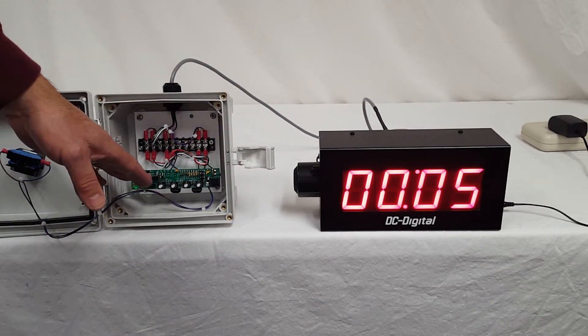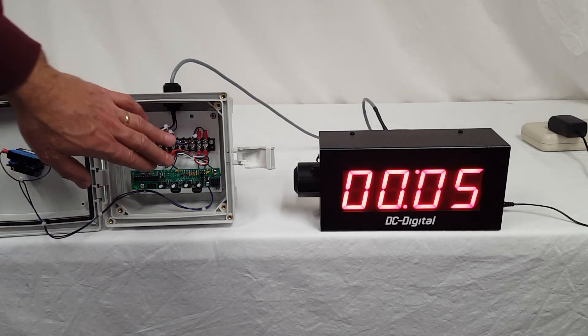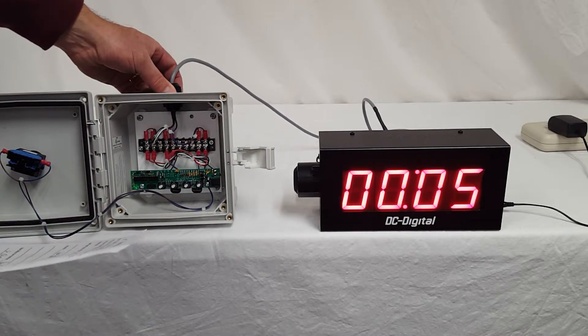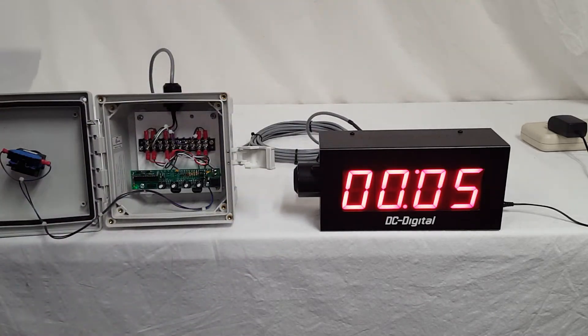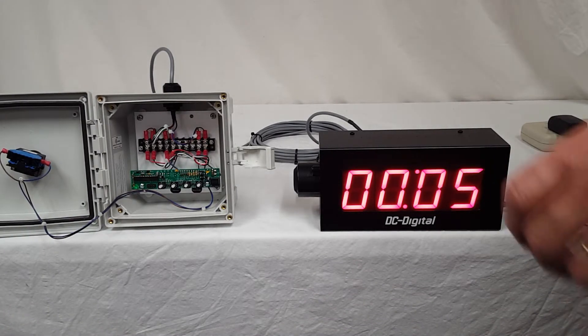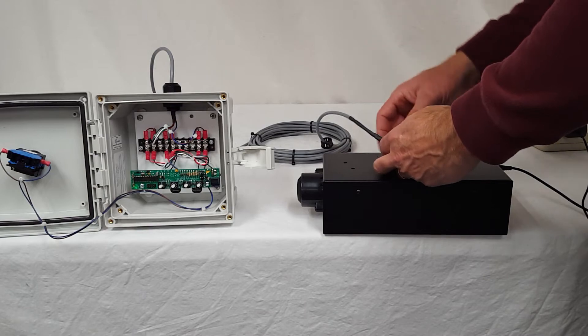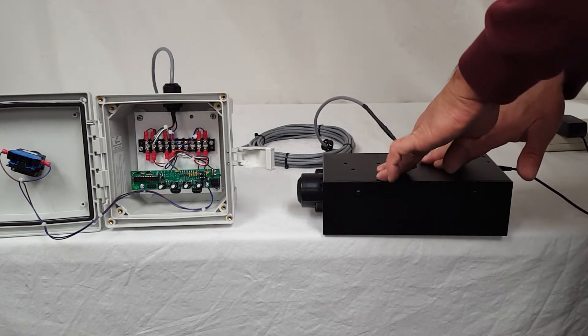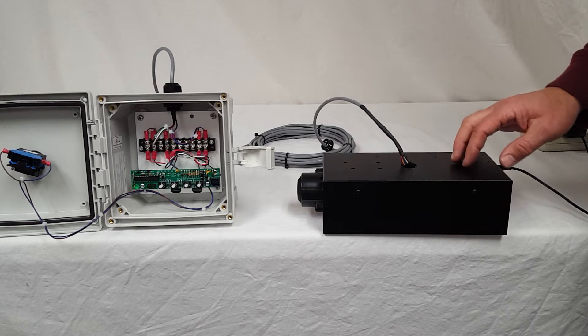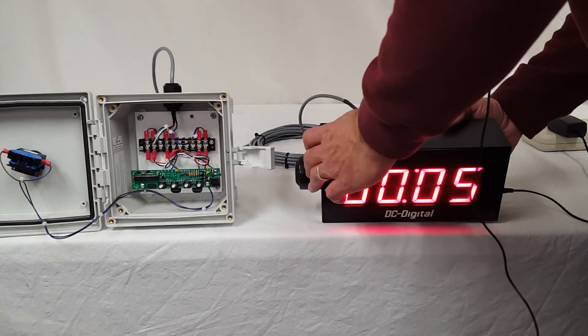What we've done is mounted the BCD switch — it usually goes inside the enclosure and is all encased — into a NEMA 4X enclosure with a terminal block. We have a cable gland with 25 feet of cable that goes right into the back of the BCD countdown timer. There's an insulator that goes over the cable and slides over the hole, so it's essentially plug and play. You wall mount this on a 2x4 or 4x4 electrical box, then run your cable through that and through the back of the enclosure.